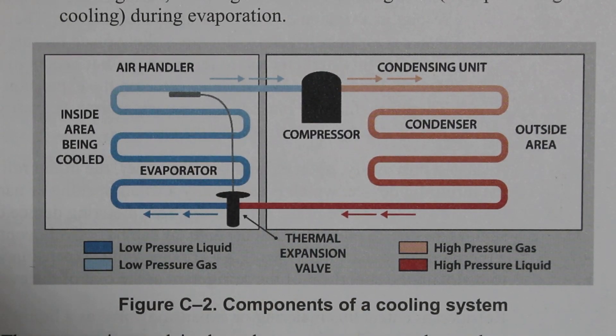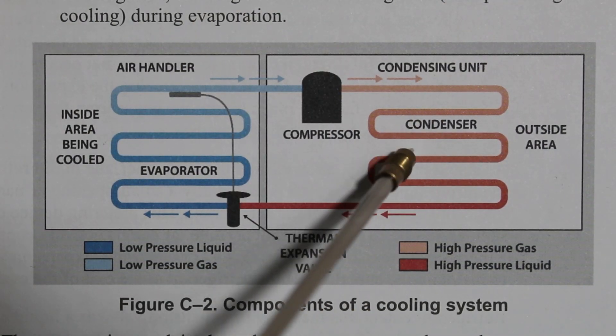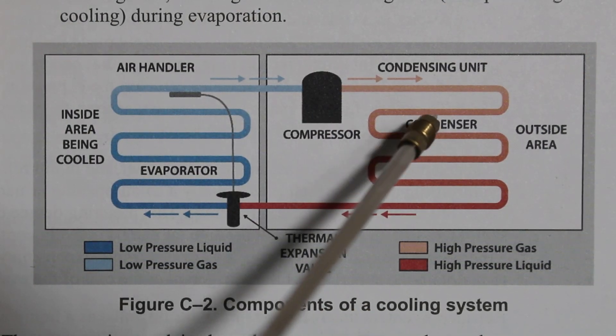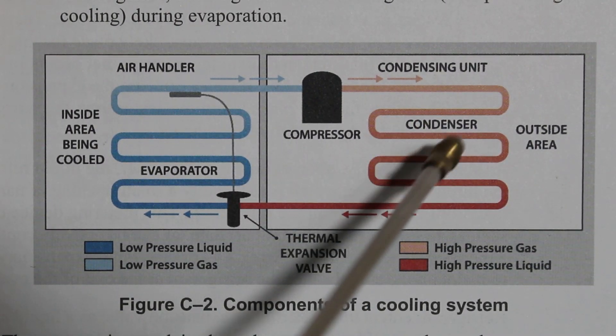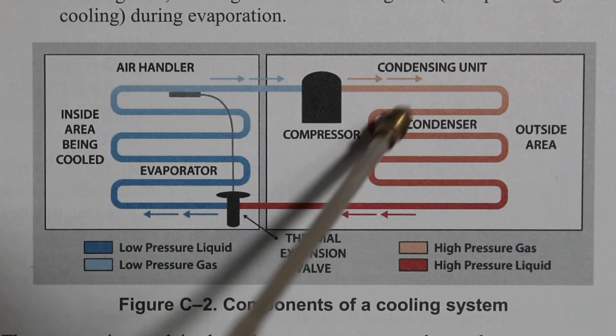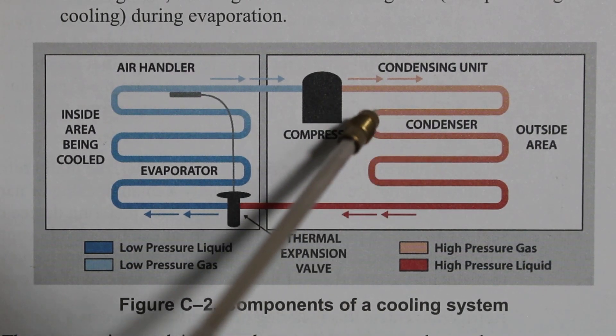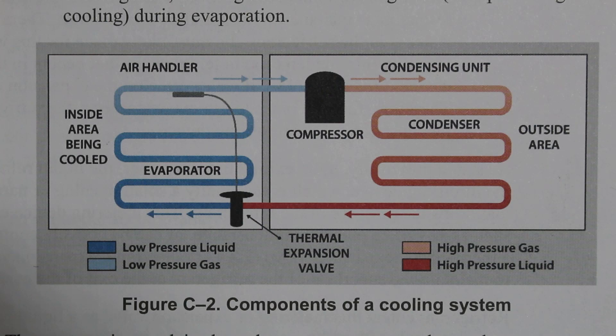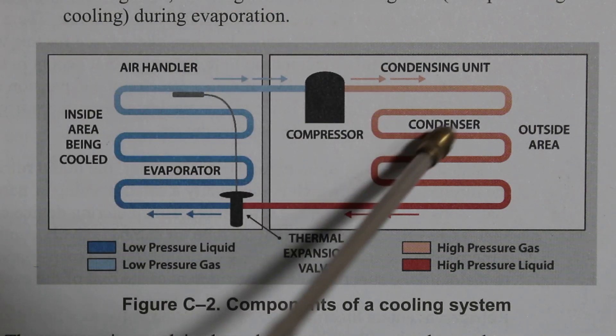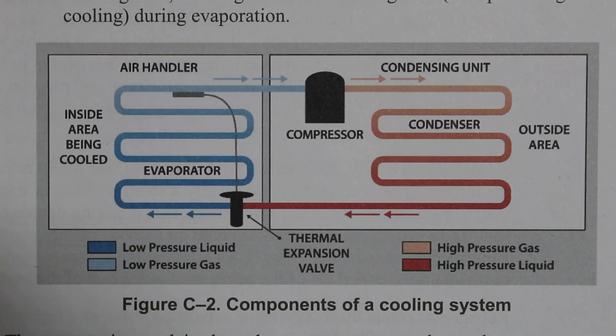Next we can move on to our second major component, and that is our condenser. Our condenser is a component where we reject heat. The most typical types of condensers are air cooled — nothing more than a copper coil with aluminum fins and a fan used to reject heat by blowing air across the condenser coil. There are also water cooled models available on the market.